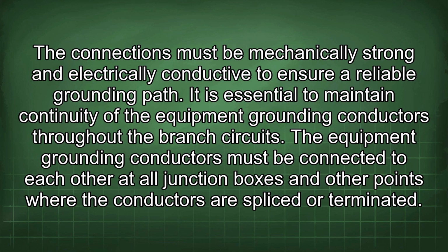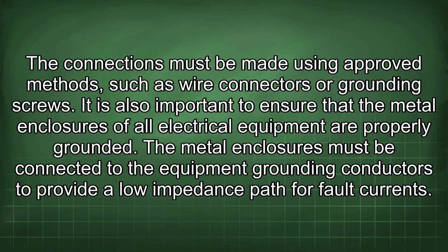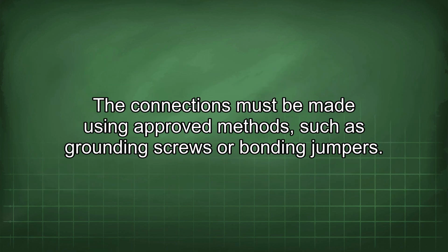It is essential to maintain continuity of the equipment grounding conductors throughout the branch circuits. The equipment grounding conductors must be connected to each other at all junction boxes and other points where the conductors are spliced or terminated. The connections must be made using approved methods such as wire connectors or grounding screws. It is also important to ensure that the metal enclosures of all electrical equipment are properly grounded. The metal enclosures must be connected to the equipment grounding conductors to provide a low impedance path for fault currents. The connections must be made using approved methods such as grounding screws or bonding jumpers.